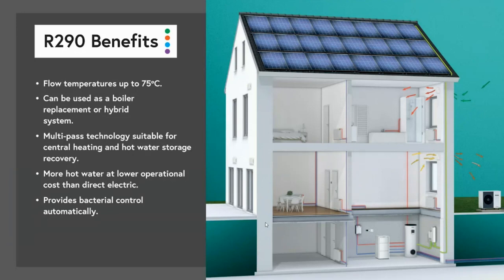So as we talked about before, multi-pass technology. That's a 5 to 10 degree differential, meaning it's getting water at sort of 55 to 60 degrees, sending it back out at 65. And it's just doing that all day long, every day, for whatever demand is coming to it, including hot water production. And for the hot water production, it's using considerably less electricity than a direct electric hot water cylinder.